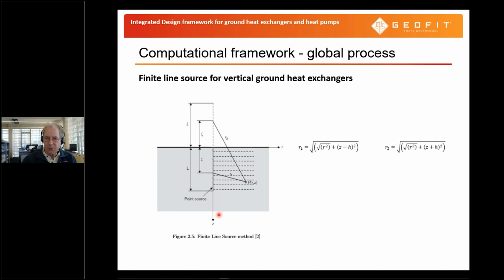How does it work, the finite line source? Well, if we imagine that this is, let's say, the soil surface, and here we have the ground volume, then we have here a borehole heat exchanger, and we can have point sources of heat that we then integrate over the whole length of the borehole. Now, obviously, at the surface, we do not want to have any temperature change induced by the borehole itself. So on top of that, we have what's called mirror sources with a negative heat demand. And if we integrate over that whole system, we get a solution for this point, for instance, in the ground; integrated, all these effects of the individual point sources can be calculated.